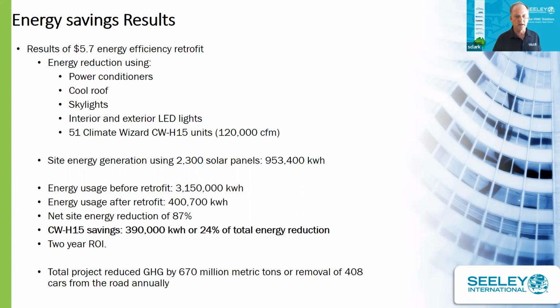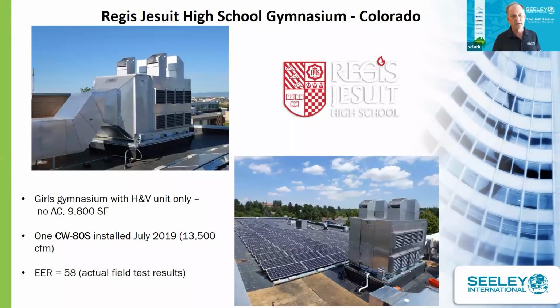Looking at a project in our backyard is the CW80S unit that was used on the Regis Jesuit High School gymnasium, where this gymnasium only had a heating and ventilation unit. This is the last building on the Regis high school campus to be air conditioned. They used a single CW80S unit installed in July of 2019. We measured the EER on a hot day, and we got 58. And that's right in line with the tables we talked about earlier, our performance tables.